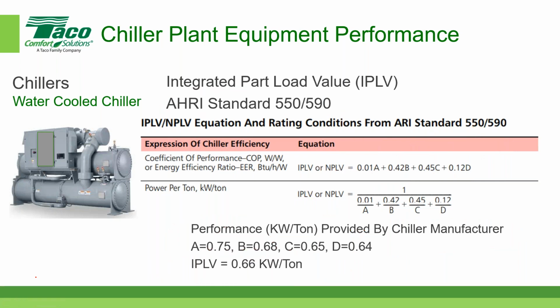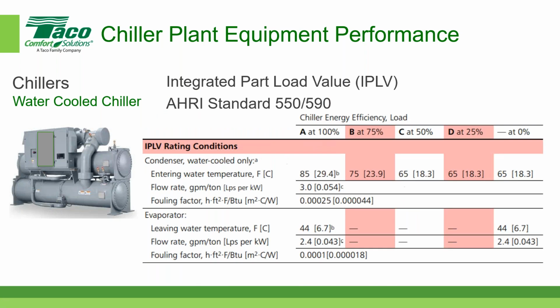It's clear as mud. Hey, can you go back one screen? Someone is questioning the fouling factor listed there. It seems kind of small, but this is from the AHRI standard, so we really don't control that, correct? Yes, exactly. This is the number that they chose for applying their standard, and the actual fouling factor could be higher or lower depending on the actual equipment that's being used. But again, the standard has to be based on everybody using the same set of values. So every manufacturer that uses exactly the same set of values under these conditions will wind up with numbers they can compare, the IPLV of one machine versus another. Good stuff.